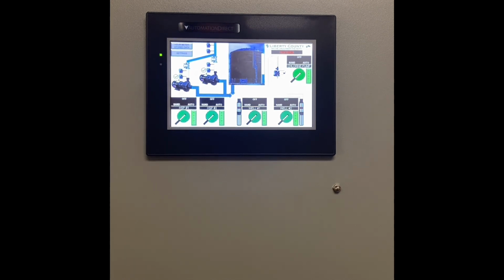They are looking for enough water pressure upstream of the check valve to manipulate the pressure switch so the system has a mechanical feedback knowing that there is indeed enough flow to warrant running that motor. We'll get to those a little bit more in detail in a second.